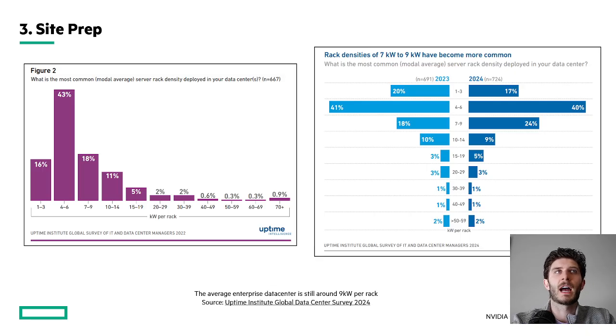The reason I say this is because the average enterprise data center, according to the Uptime Institute, still runs at 9 kilowatts or below. That's 75% of all data centers globally, if you consider the 2022, 23, and 24 surveys from the Uptime Institute to be representative. Much less than 5% of the industry is able to run average server rack densities above 40 kilowatts.